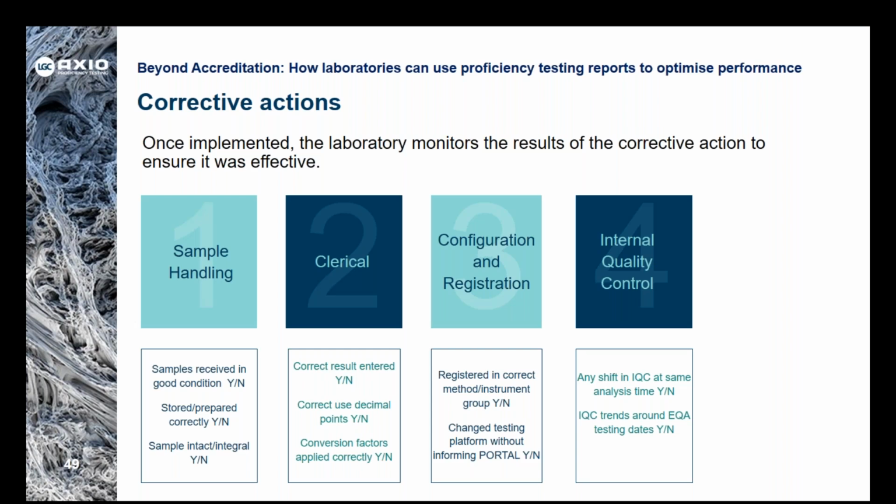Typically, the checklist will guide the user from the more typical non-conformance issues through to the more challenging potential causes. Whilst we're not showing the specific corrective action to take, these are the questions that, once answered, will lead us to identifying the corrective action to implement. For example, looking at sample handling, are we physically inspecting each vial that arrives to check that it is integral? That, for example, there is no lysing of whole blood, no leakage, no cracked vials, which could all potentially contaminate the sample. If we identify the cause, we will apply the corrective action and record the event.